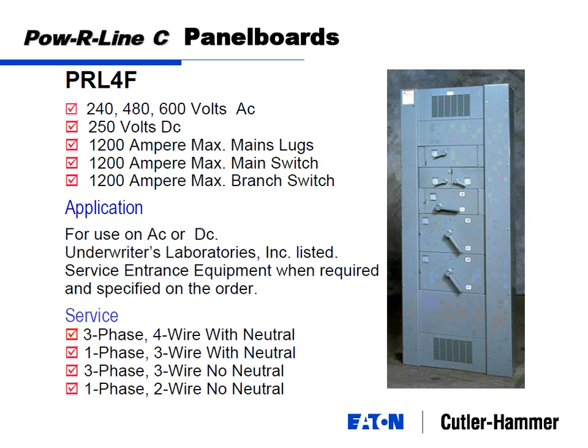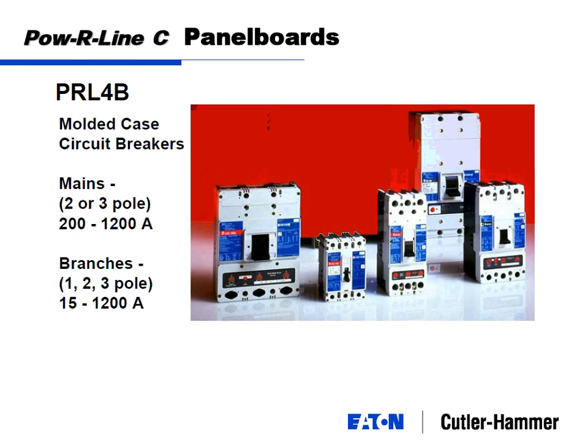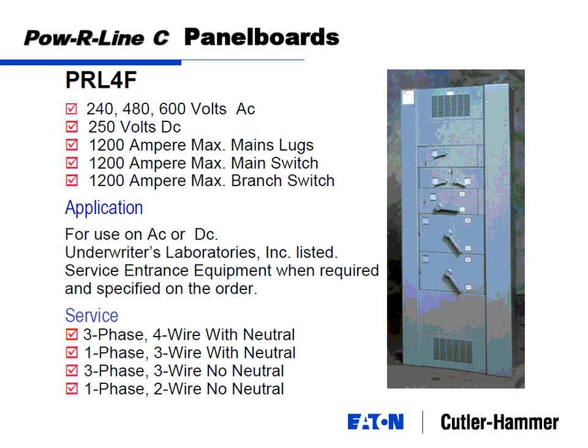Okay, the first one I showed you was called the 4B. I think it was called the 4B. Yeah, 4B. Okay, this one's called the 4F. And what would be the difference? Breaker for B, fusible for F. The panelboard is exactly the same, no difference. You can see from the front, instead of a breaker handle coming through, you've got a switch handle. So when I talk fuses, it's always switching fuses. There's blades that go in and out with fuses in there for protection. Because you've got switch and fuses, the size is going to be notably different. Same ratings across the board up here.